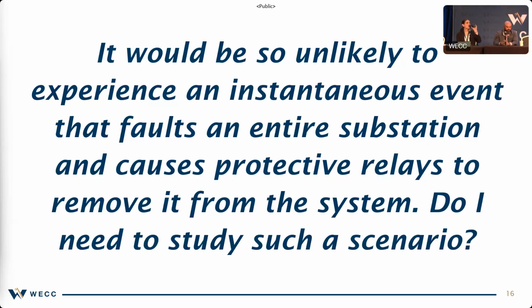On that subject, here's a hypothetical. The likelihood of something like an instantaneous event that faults an entire substation—poof, smoking hole, gone—so unlikely. Why are we studying this? Do I need to study a scenario of a smoking hole, a complete loss of service? There's something to be said for what is instantaneous to a normal person observing an event versus what the system sees electrically.